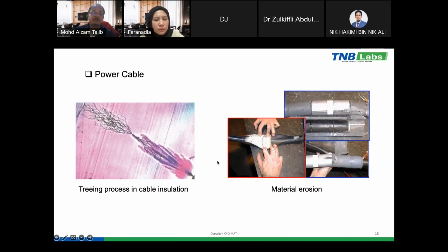And then for the power cable, through partial discharge testing, PD testing, we are able to detect the treeing process in the cable insulation. From the previous video, we can see that when treeing occurs from the conductor, it can cause the stream to touch the ground, and then it will cause the failure of the power cable. The partial discharge can also cause material erosion, which finally can cause the failure of the cable joint.